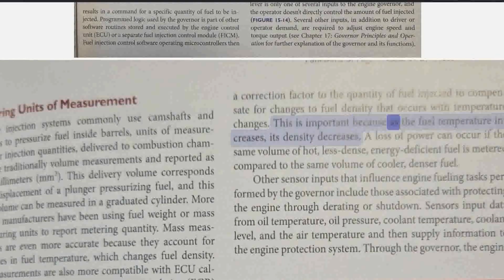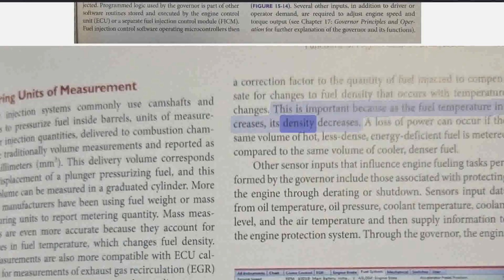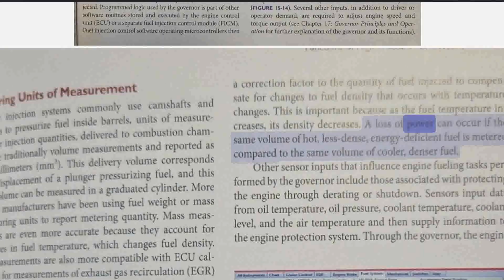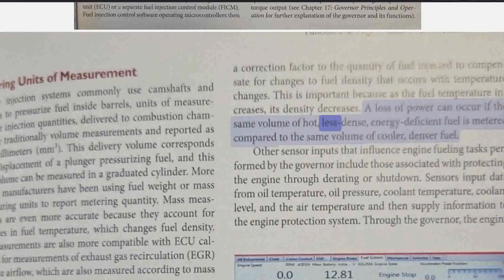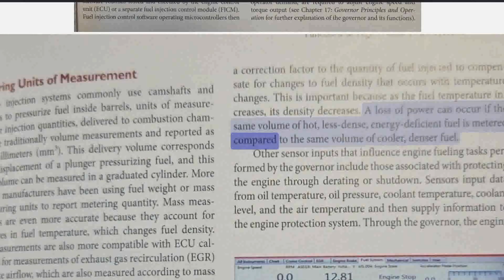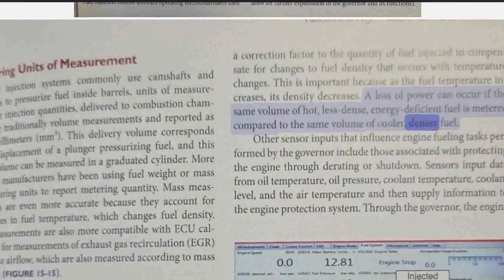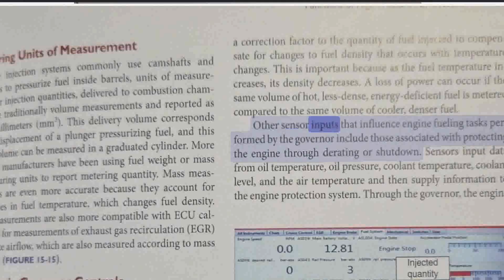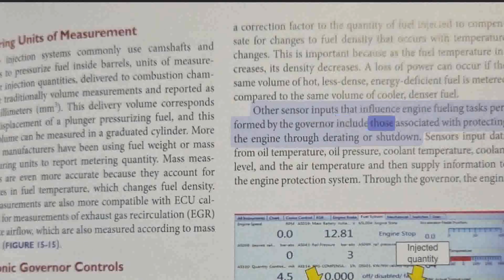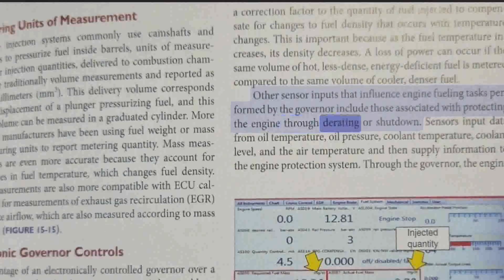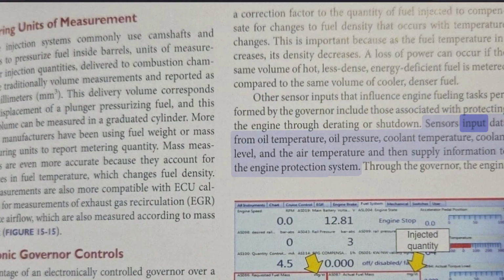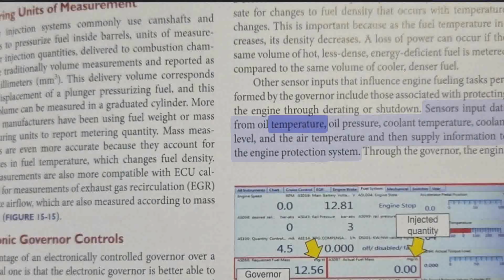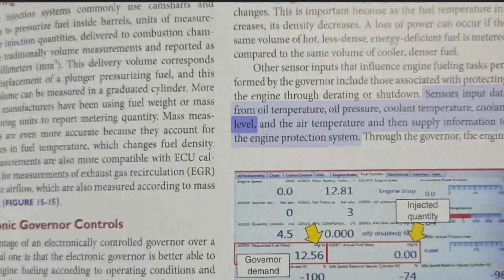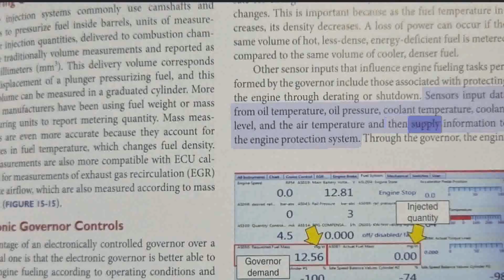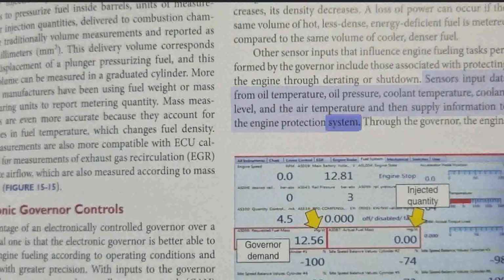This is important because as the fuel temperature increases, its density decreases. A loss of power can occur if the same volume of hot, less dense, energy-deficient fuel is metered compared to the same volume of cooler, denser fuel. Other sensor inputs that influence engine fueling tasks performed by the governor include those associated with protecting the engine through derating or shutdown. Sensors input data from oil temperature, oil pressure, coolant level, and the air temperature, and then supply information to the engine protection system.